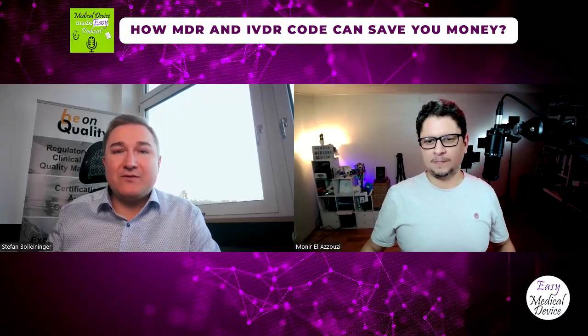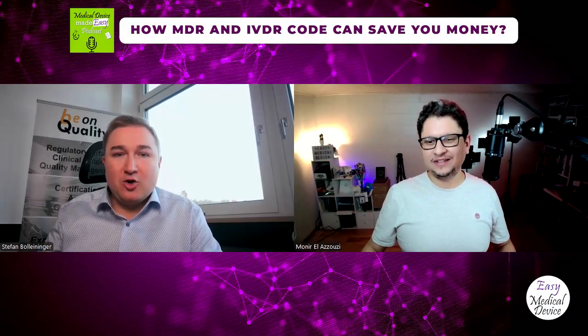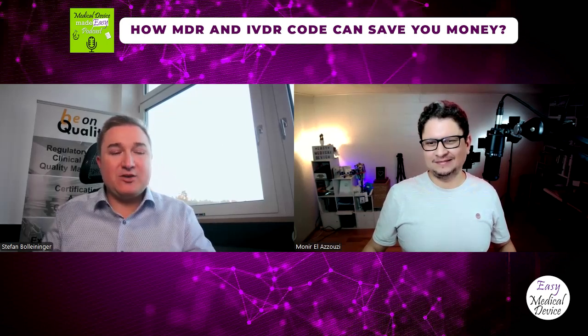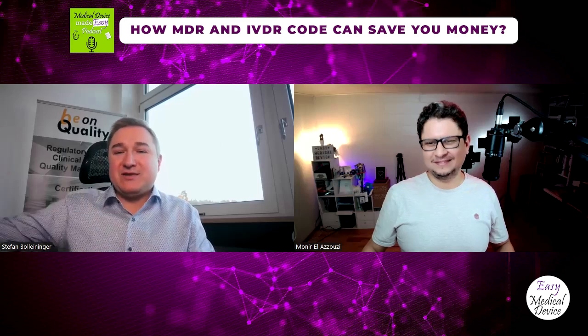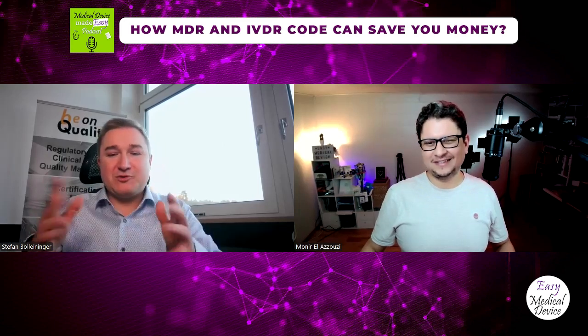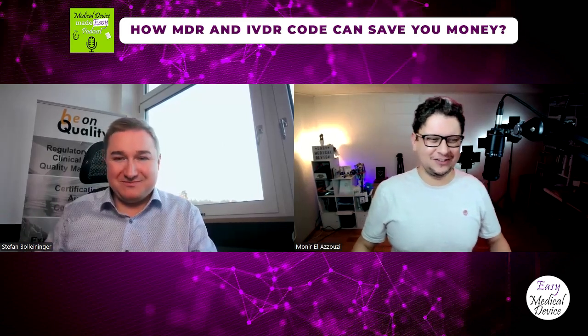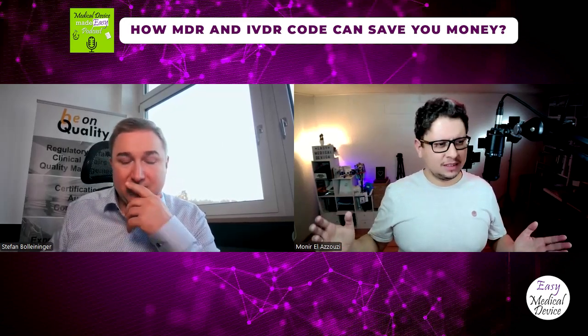There was a calculation with MDD already in the past, so that a very big manufacturer told me once that, well, we assume based on our codes and whatever we have, that each product will be sampled each 12 years. Okay, 12 years. We know the product, I can tell you when I bring it on the market, I have a likelihood that this product will be challenged every 12 years. Okay. So, depending how many products you put on the market. Great. Good to know.